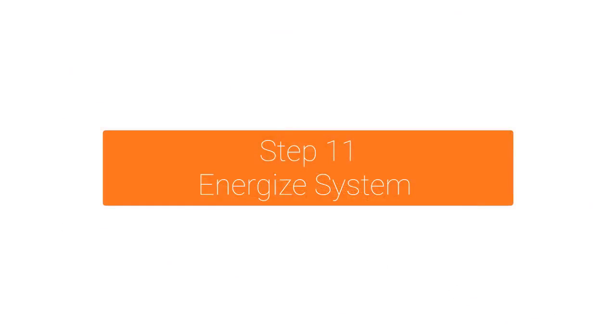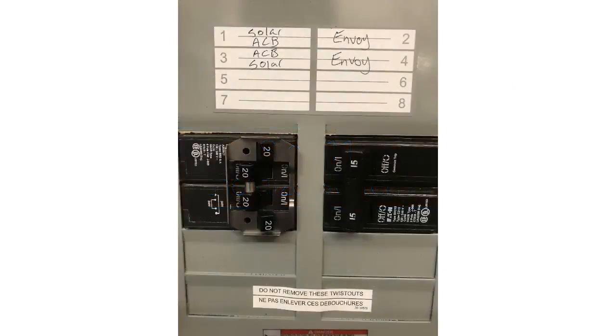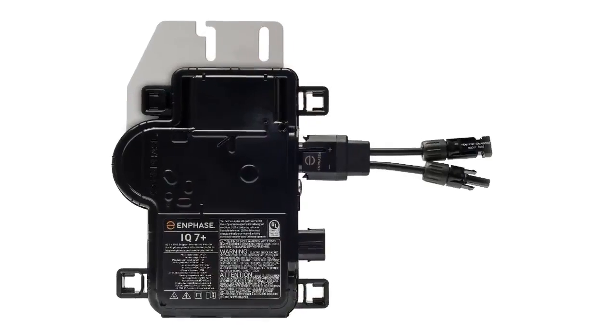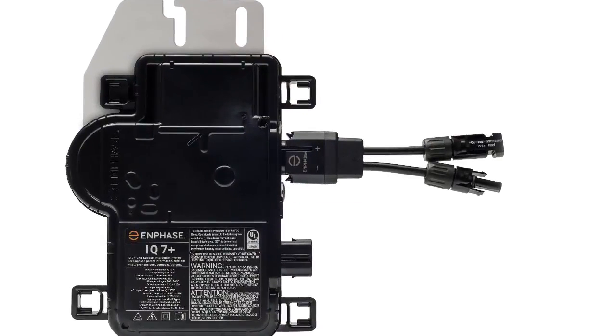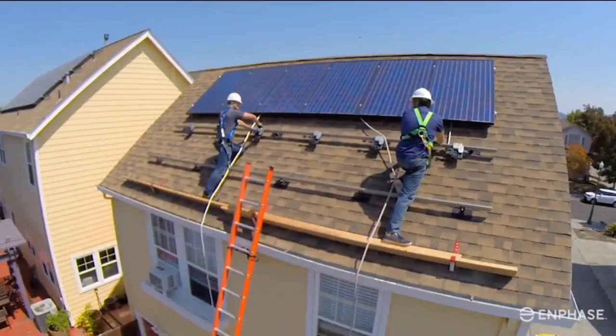Turn on the AC disconnect or circuit breaker for the branch circuit. Turn on the main utility grid AC circuit breaker. Your system will start producing power after a 5-minute wait time. The status LED on the side of each IQ microinverter will blink green 6 times to indicate normal operations after DC power is applied. You've now completed the rooftop installation of the Enphase IQ Microinverters.